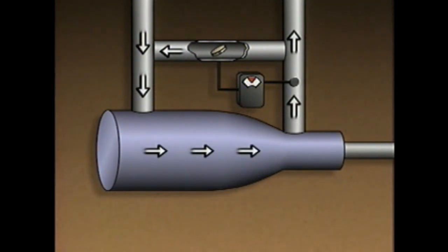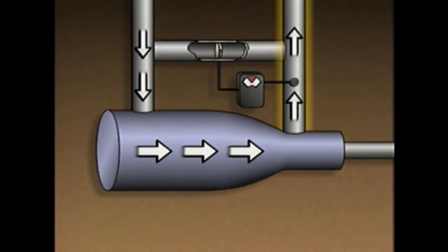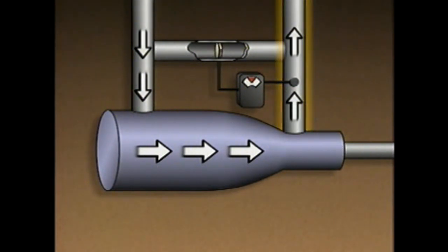When demand increases, gas flow through the compressor also increases. When the gas flow is high enough to prevent surge, the flow controller closes the recirculation valve. The gas flow from the compressor is then directed only through the discharge piping.